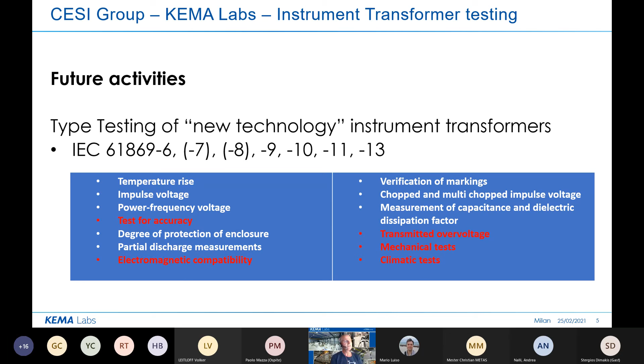So what we did at the KEMA laboratories, the high voltage, high power and smart device laboratories, is implement for ourselves the 61850 network. We have implemented a timing network so that we at least can cope with this kind of aspects, the PPS, the PTP type of time synchronization. Maybe you can also imagine that when speaking about mechanical testing, climatic testing, or transmitted overvoltage measurements, you cannot do that simply in the traditional way anymore, because again, we are moving from analog to digital, and that also requires completely new approaches for this kind of testing.